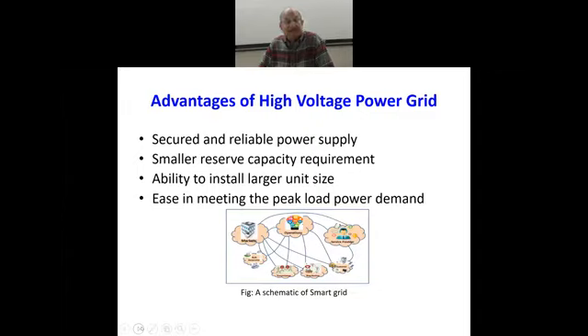The power generation by a single unit of 650 megawatt would work out to be much more economical. So it is desirable to install larger unit sizes, but if a larger unit goes out of the circuit, the whole system gets such a jolt that it may not be able to withstand it and continue the supply of power to the consumer. But when the total handling capability of the grid increases, we can also install larger units. That is why the single largest unit should be something between 5 to 10% of the total power handling capability of the system. So that also increases.